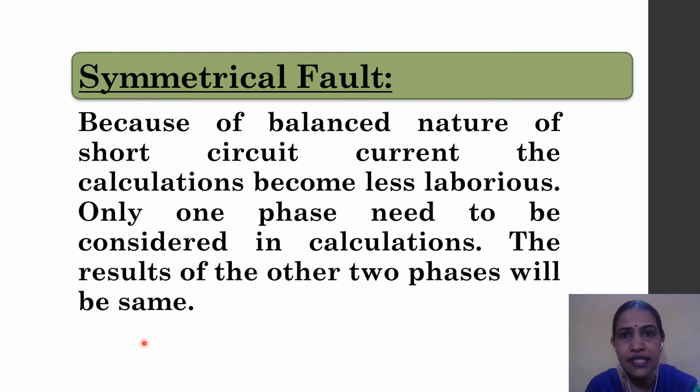And why symmetrical fault current? Because it is very severe in nature. There are different types of faults, but a three-phase fault is very dangerous. Very heavy current flows through such a fault, and that is why our main concentration is on symmetrical fault. We consider symmetrical fault while selecting circuit breakers or different types of protective devices.